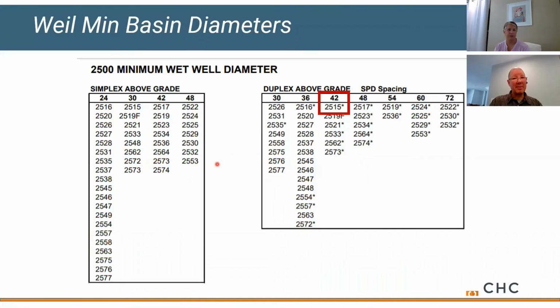One thing to keep in mind, depending on the equipment we select, it may take up some space. It may not fit in a 36-inch diameter basin. We might need to go to a larger basin size just to fit the equipment inside. So pulling in a manufacturer's rep to help you with this is a good thing. There are some resources we can throw at you. I can tell you that the 2515 requires a minimum of a 42-inch diameter basin. So even though 36 might have worked for us, we need at least a 42-inch in order to physically fit the equipment.